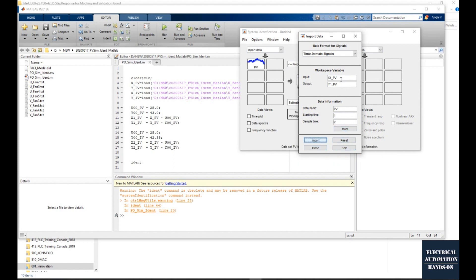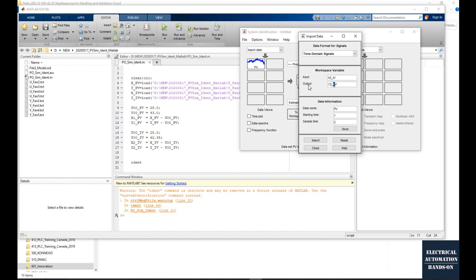The output data, that is our process value feedback data. In my case, the output is the temperature value. Usually to identify the process model, we need two groups of input and output data. The first group will be used to identify the model. The second group will be used to verify the model.